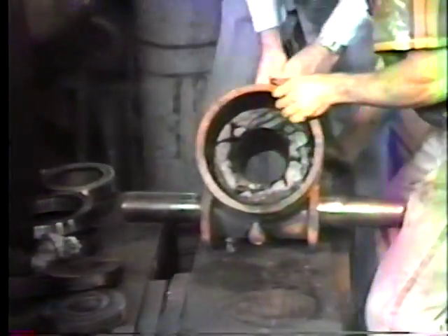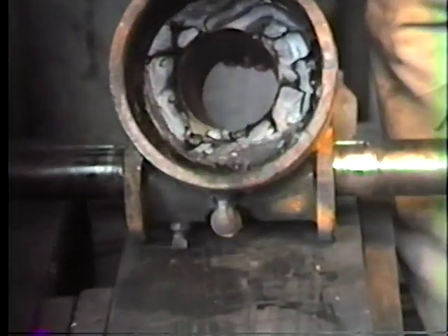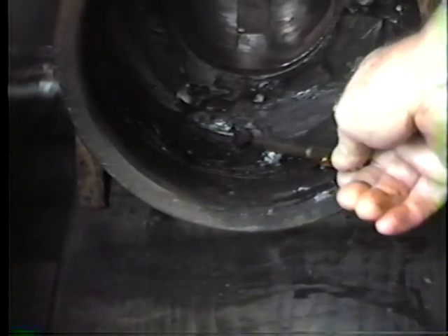I want to see it. All right, tip that thing towards me if you would. There's the air seal right there. Is that thing plugged? It's got grease in it. It's not solid, but it's partially filled with viscous type grease. Not hard. Okay, but it is plugged. Right. All right, thank you.